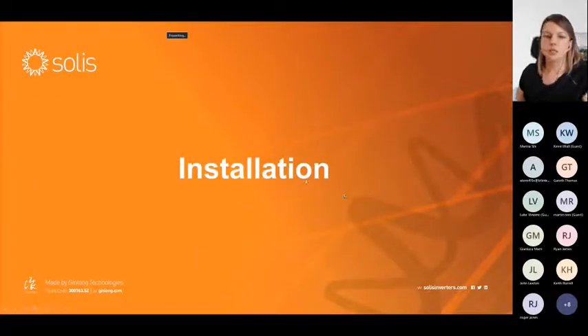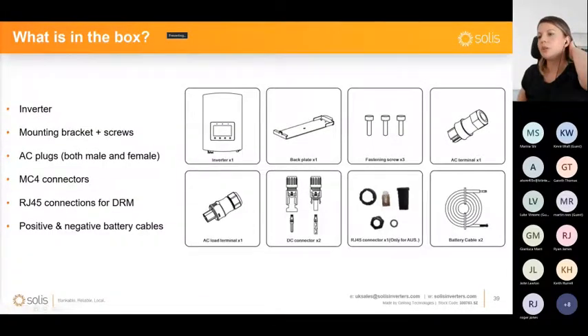So let's go a little bit to the installation. I'm just going to show you what you can find in the box that comes with the inverter, what's not in the box, and what would be the main things that you should look out for. I think most of these you already know, but I want to make sure they're put through here as well. So definitely you're going to find in the box the inverter, mounting brackets, the AC plugs for both main AC and backup, and MC connectors, both on the inverter side and on the cable side.